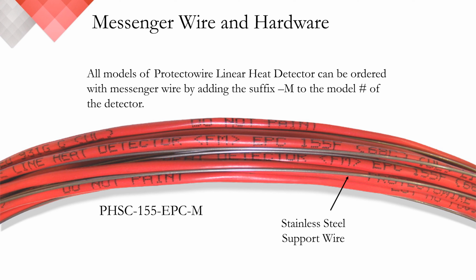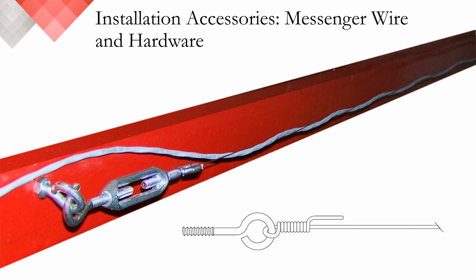When using messenger wire, turnbuckles and eye bolts must be employed at each end of a straight run to apply the appropriate amount of tension to support the detector over these long spans. The maximum length between turnbuckles should not exceed 250 feet or 76 meters. And the wire must also be supported with the approved intermediate fasteners at intervals typically ranging anywhere from 15 to 20 feet or 4.5 to 6 meters. The final spacing of intermediate fasteners is largely determined by the individual application.